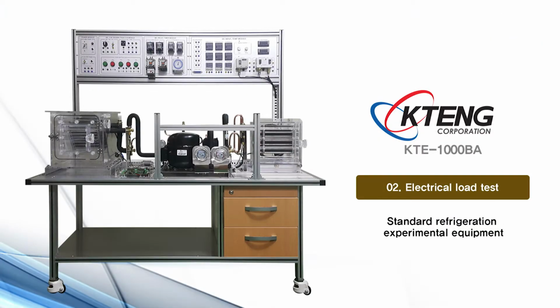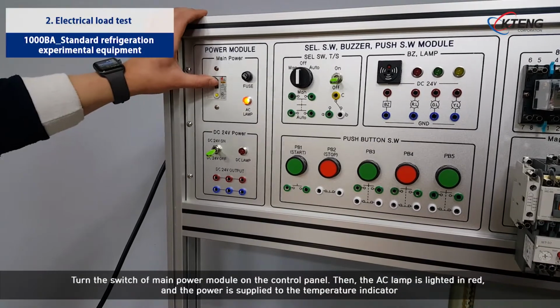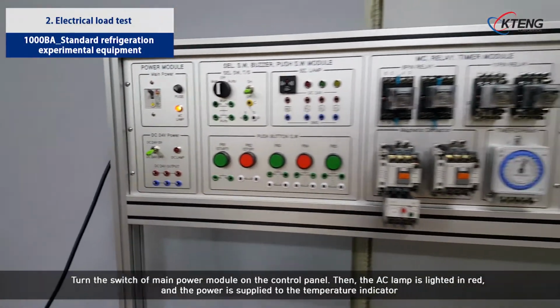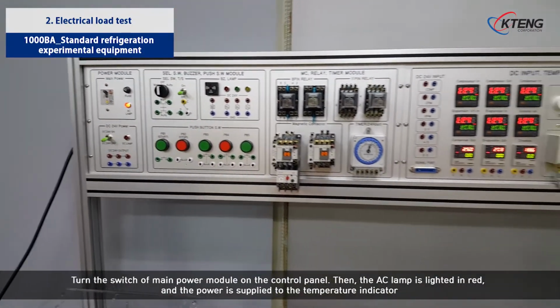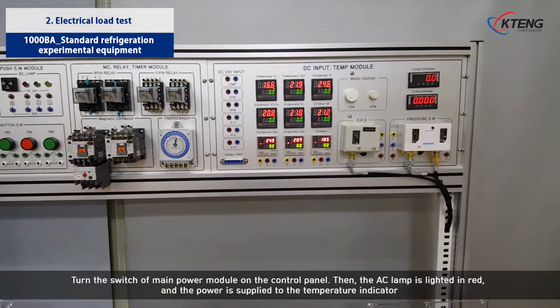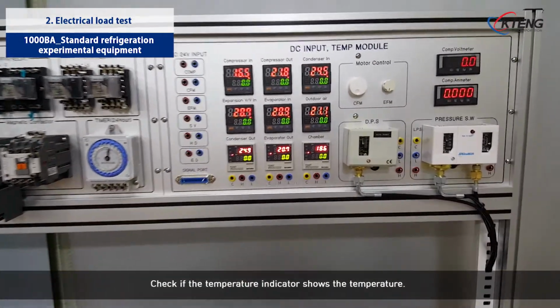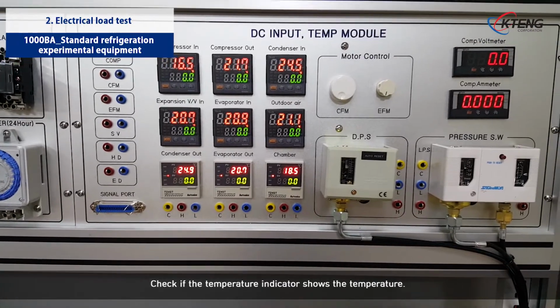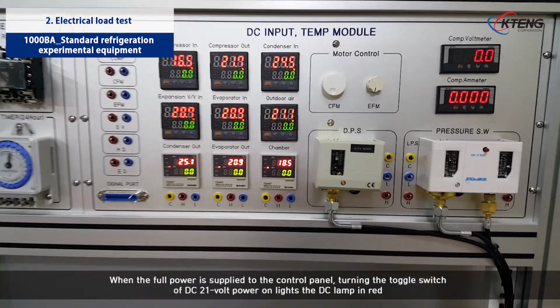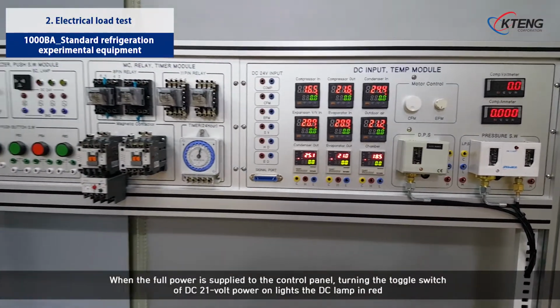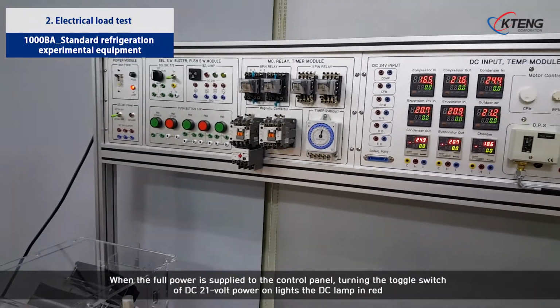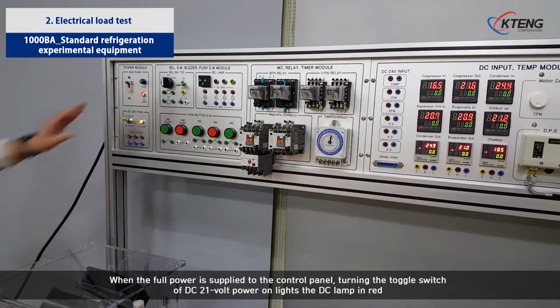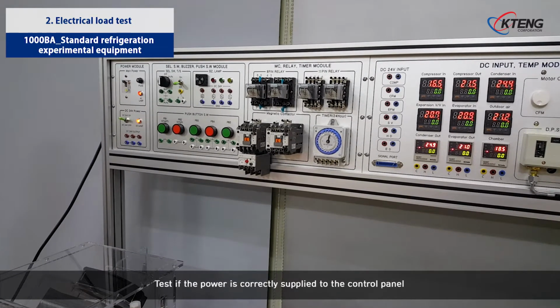The following describes the basic operation of the standard refrigeration test equipment. Turn on the switch of the main power module on the control panel. Then the AC lamp is lighted in red, and the power is supplied to the temperature indicator. Check if the temperature indicator shows the temperature. When the full power is supplied to the control panel, turning the toggle switch of the DC 24-volt power on lights the DC lamp in red. Test if the power is correctly supplied to the control panel.